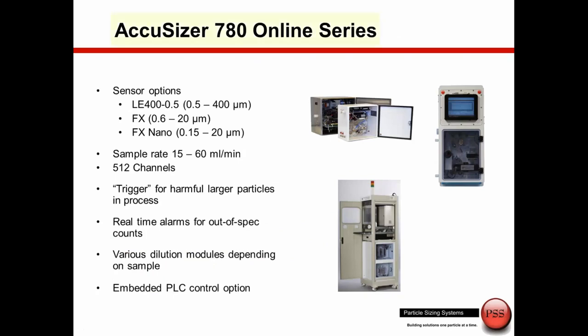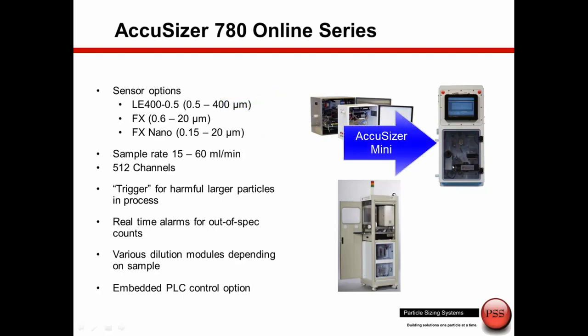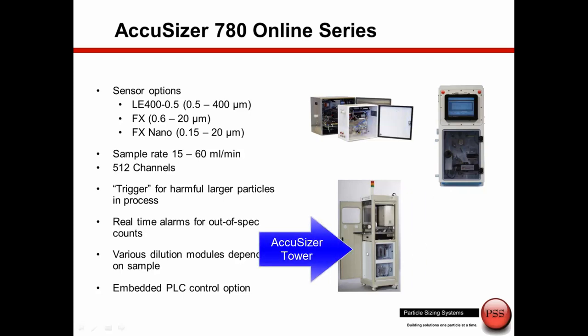Any of the sensors discussed today — the LE400, FX, or FX-nano — can also be mounted online for in-process measurements, either measuring the sample undiluted or with dilution. Systems are available for single-point monitoring, such as the online AccuSizer and the mini system popular for CMP slurry monitoring. A tower system can multiplex four different fluidics lines into one system, monitoring up to four different CMP slurry lines. Everything is fully automated with reporting, alarming, and output to programmable logic controllers.